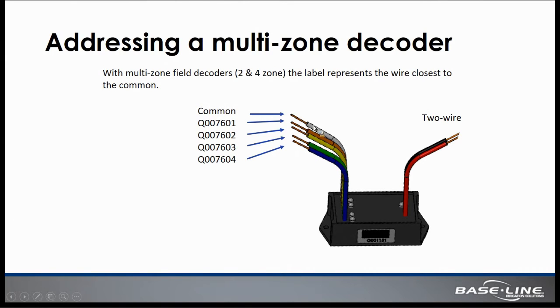When dealing with decoders, it's a different configuration than with conventional wire, because decoders come in different shapes and sizes. So baseline manufactures decoders in a 1, 2, and 4 station configuration, and since a decoder has the ability to run or operate multiple control zone valves, the decoder itself needs to have a serial number sequence associated with it, so the controller knows which valve it is actually interfacing with.